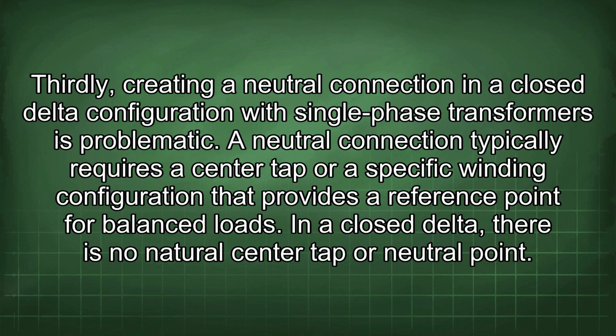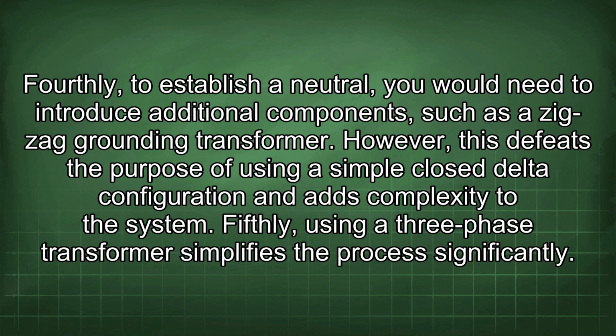Thirdly, creating a neutral connection in a closed delta configuration with single-phase transformers is problematic. A neutral connection typically requires a center tap or a specific winding configuration that provides a reference point for balanced loads. In a closed delta, there is no natural center tap or neutral point. Fourthly, to establish a neutral, you would need to introduce additional components such as a zigzag grounding transformer. However, this defeats the purpose of using a simple closed delta configuration and adds complexity to the system.